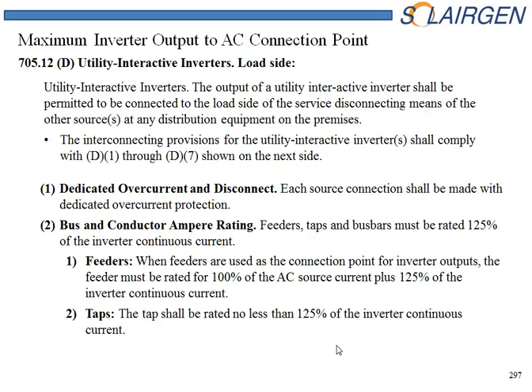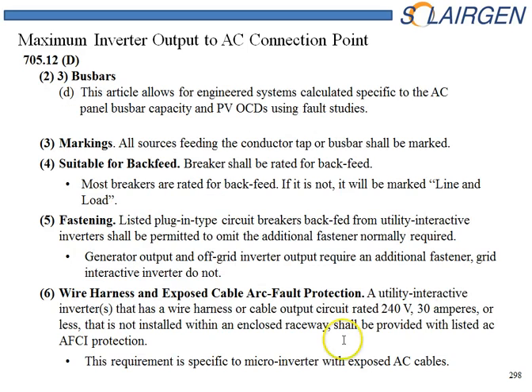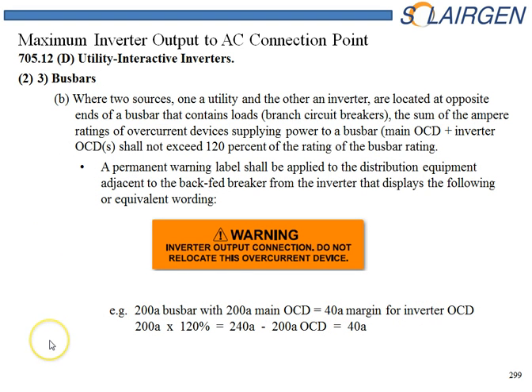Now let's take a look at connecting on the load side, the most common way that we connect for residential and commercial systems. We're going to back feed one of the main panels. So we have to look at the capacity of this bus bar rating and not exceed it, or exceed it only in the permissive ways that the NEC allows us to.